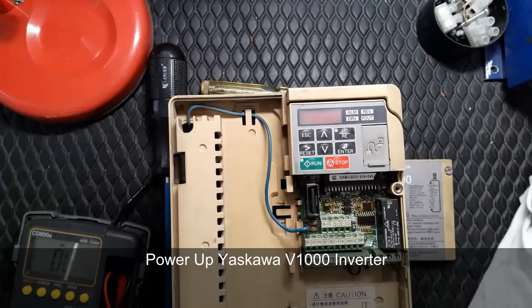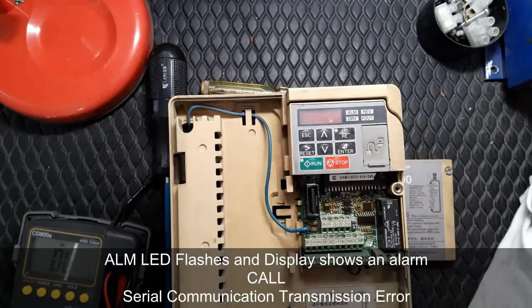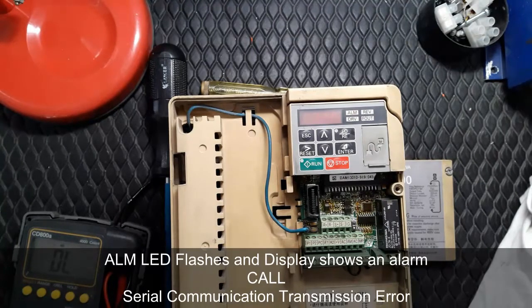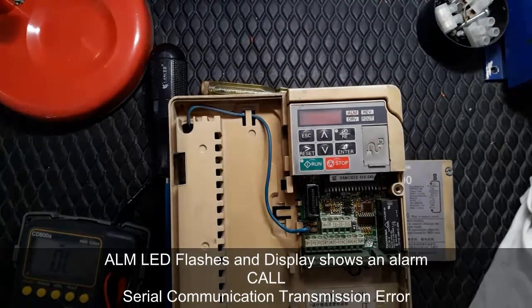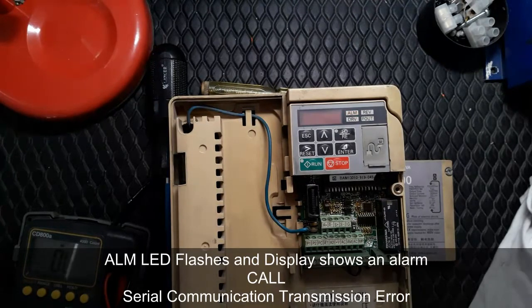Power up the Yaskawa V1000 inverter, and here it flashes an alarm, shown as CALL alarm, which means serial communication transmission error. Actually, this inverter has a communication connection, but we want to use it by external and keypad mode. I need to initialize this inverter.